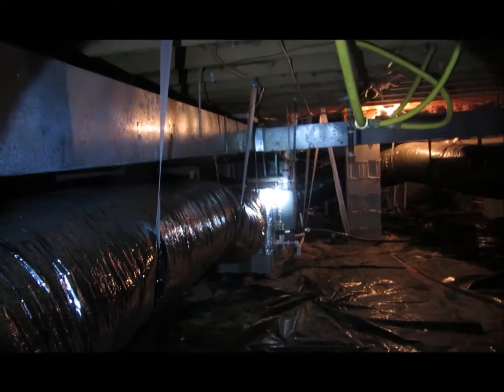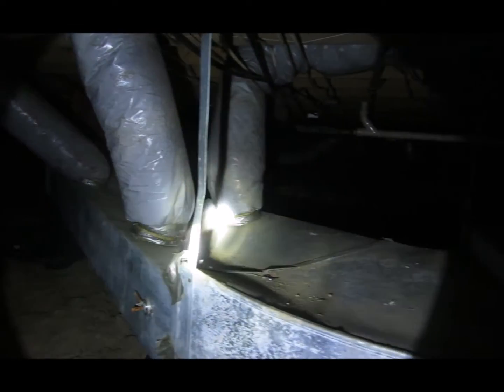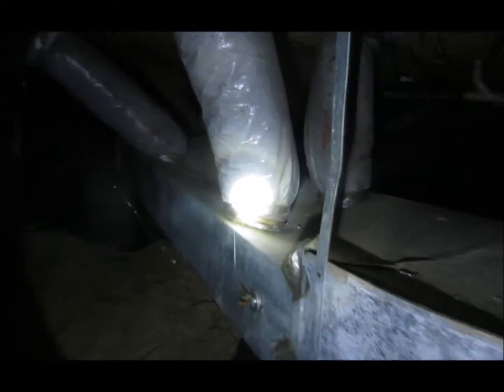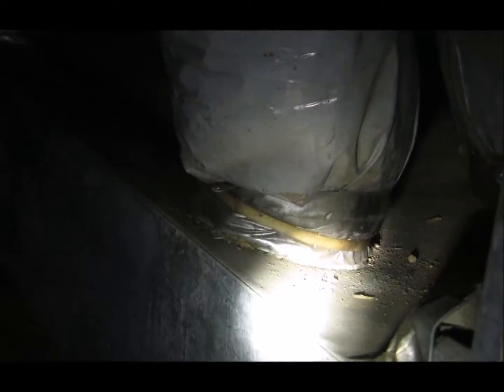There's some new flex associated with the new air handler, and then there's old original 4.2 R value flex duct that has mold growing on the outside of it, and the joints are not sealed. Recommendation would be to replace the secondaries, clean and resurface the main trunk.